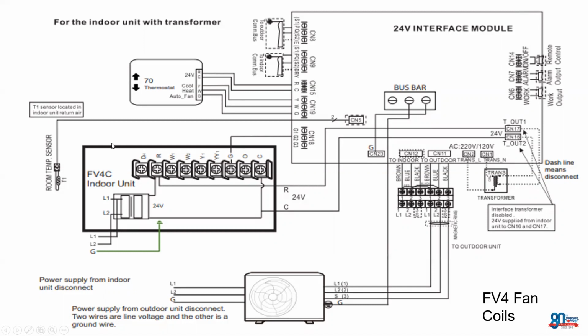Okay, from there, let's go over to our FV4 printed circuit board. Now you'll see on here, this already has a step-down transformer, stepping down to 24 volts for control voltage. So what we're going to do in the field is take thermostat wire from R and C, take that right out of the outlet of the transformer, and wire that into the appropriate R and C terminals at the FV4 indoor unit.